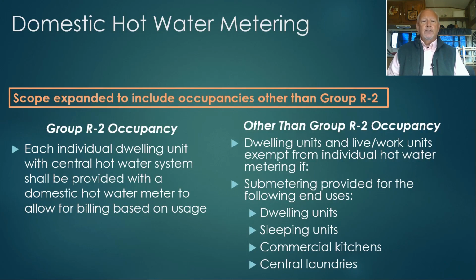Another change on the service water heating system is domestic hot water metering. The scope has been expanded to include occupancies other than Group R2 in the 2015 Washington State Energy Code. This requirement was only for Group R2 occupancies, and that remains the same. Each individual dwelling unit with central hot water systems shall be provided with a domestic hot water meter to allow for billing based on usage within that dwelling unit. That requirement, though, has been extended to dwelling units in other than Group R2 occupancies, so either individual dwelling units or live-work units.